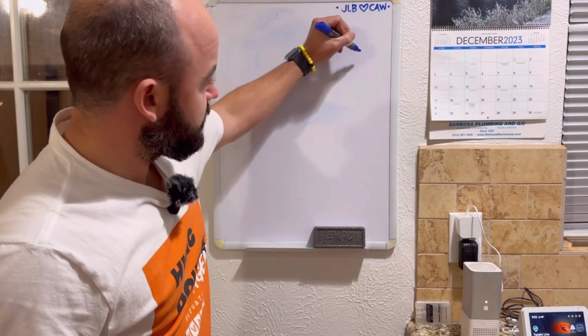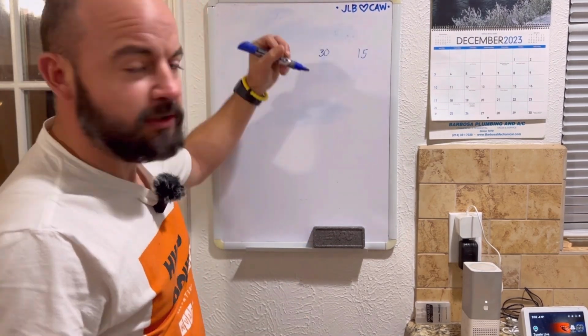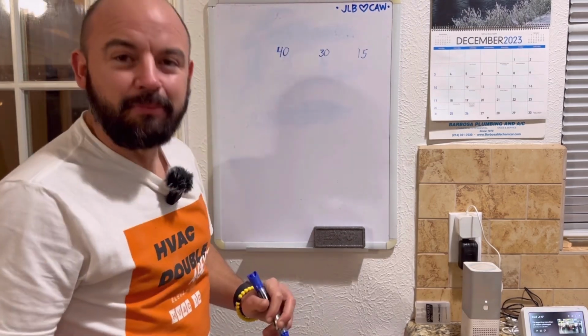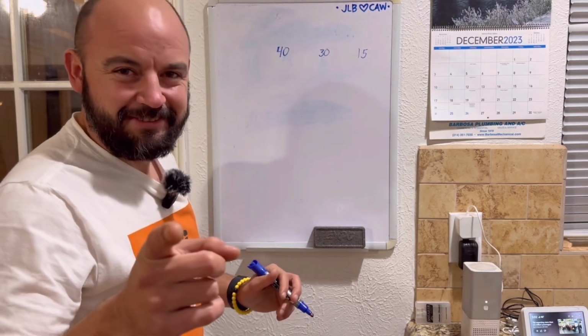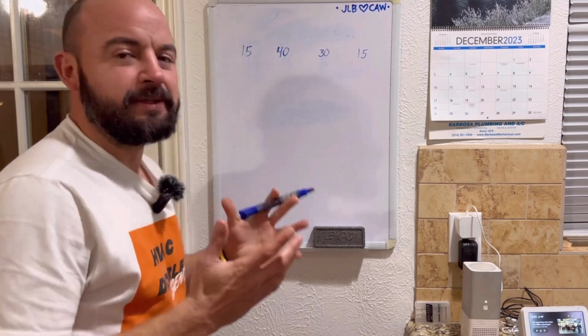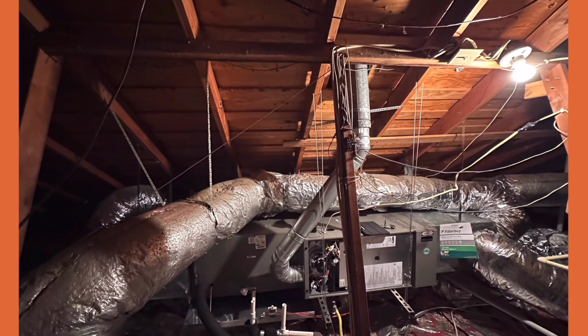You turn 15, then you turn 30, then you turn 40, but you always act like you're 15. What does this mean? 15% of your static pressure goes to your return ductwork, 40% goes to your air filter, 30% goes to your evaporator coil, and 15% goes to your supply duct.